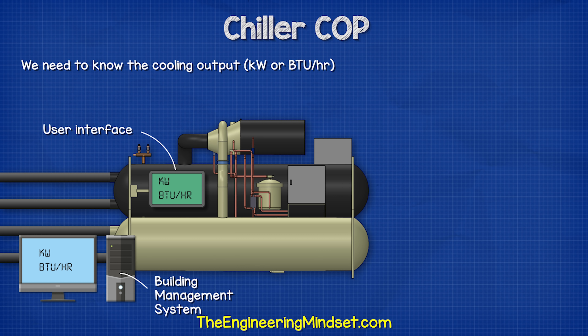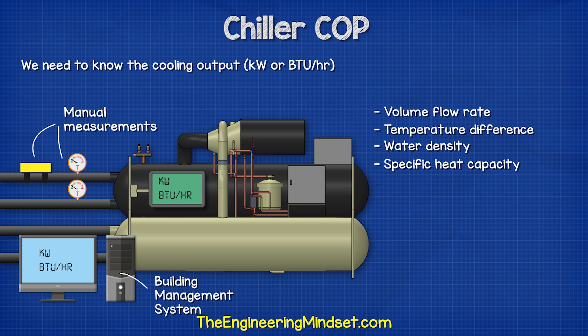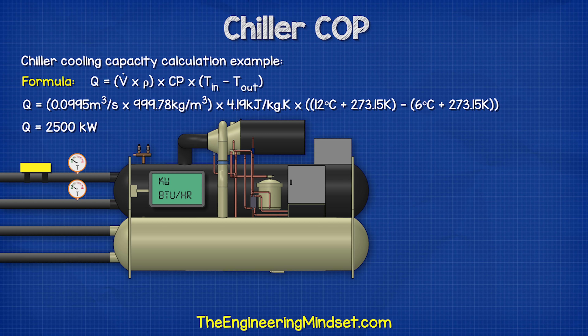Alternatively, if this information is not available, we would need to calculate it by taking some manual measurements for the volume flow rate of the chilled water, then look up the water density and the specific heat capacity, and then measure the difference in temperature between the water entering and leaving the evaporator. That is beyond this video but I'll just show you a sample calculation for how this is done.